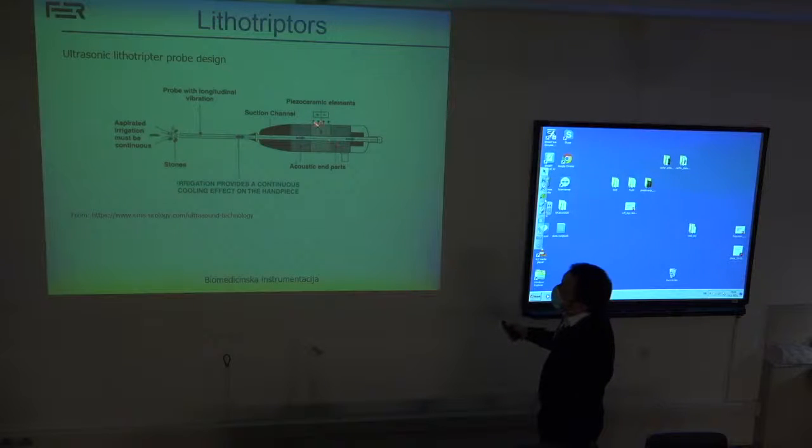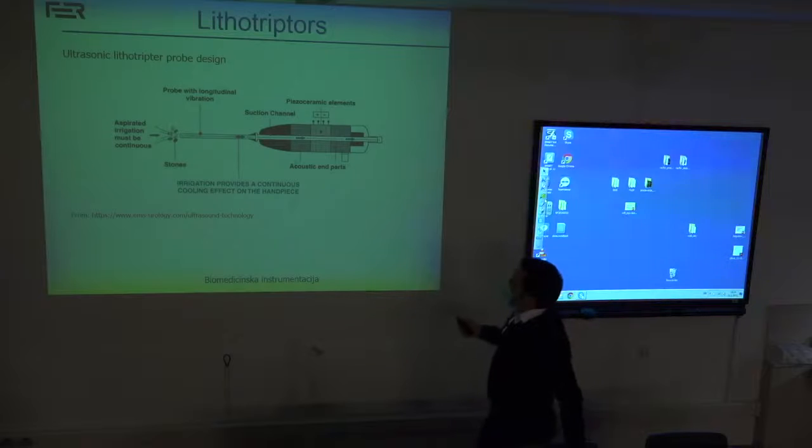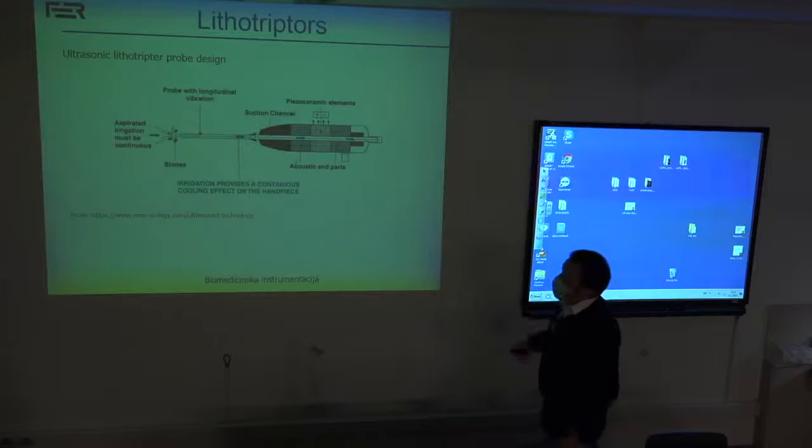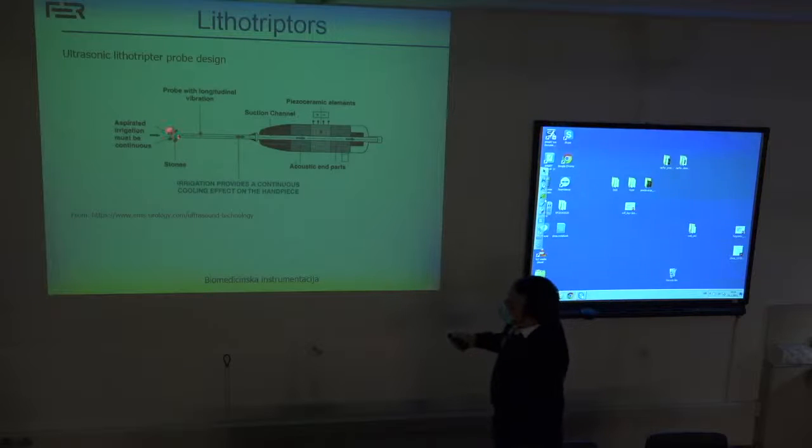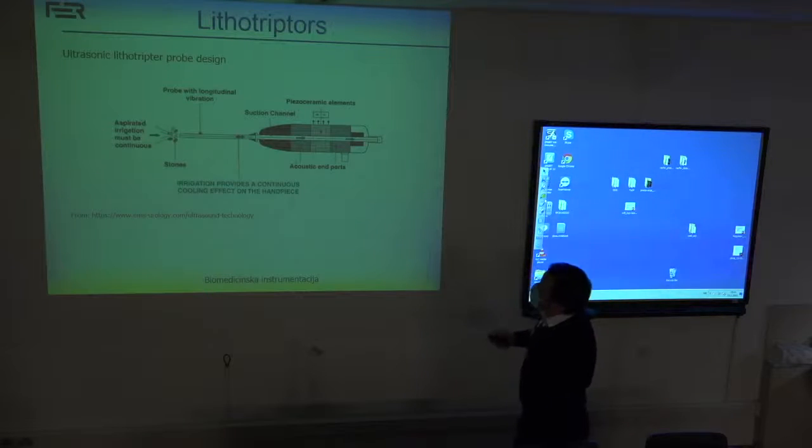These are the piezoelectric elements where you again come with some kind of power supply. So this part is then actually vibrating. The vibrations are then transferred through this rod, and they come into contact with the stones. And then the electrical part, there is some kind of a motor that is enabling suction, so that all these particles are then sucked into this tube and actually taken out of the body.